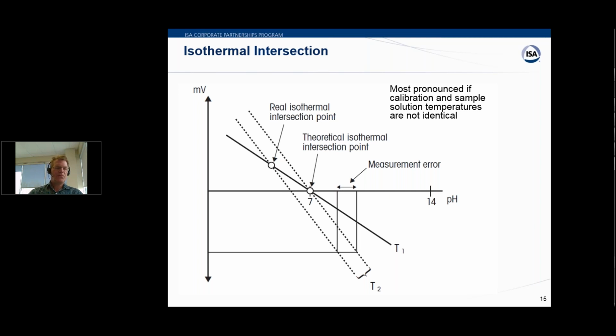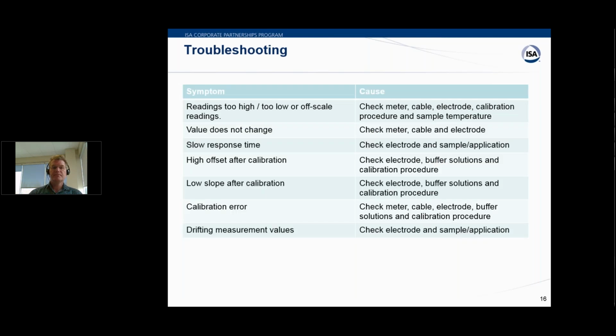However, if we have a difference in temperature when we calibrate, what you'll see is that the slope will change and then we'll be on the dashed line. So we would be calibrating and measuring on two different curves, which will introduce error into our measurement. And so it's just some other troubleshooting things besides the measurement that you see here.